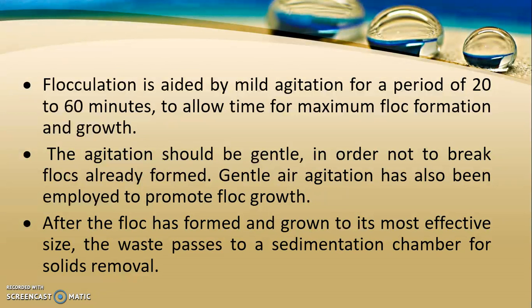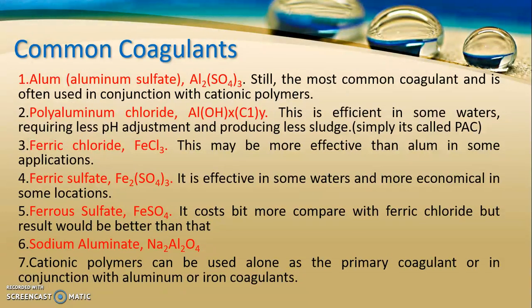Gentle air agitation has also been employed to promote floc growth, so that if we provide gentle mixing there will be collision between the flocs and the colloidal particles, forming bigger and bigger flocs. After the floc has formed and grown to its most effective size, the waste passes to the sedimentation chamber for solids removal, where these larger flocs settle down by gravity. Common coagulants include alum (aluminium sulphate), polyaluminium chloride, ferric chloride, ferric sulphate, ferrous sulphate, sodium aluminate, and various cationic polymers.